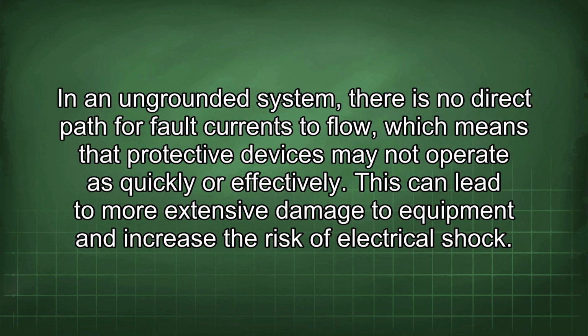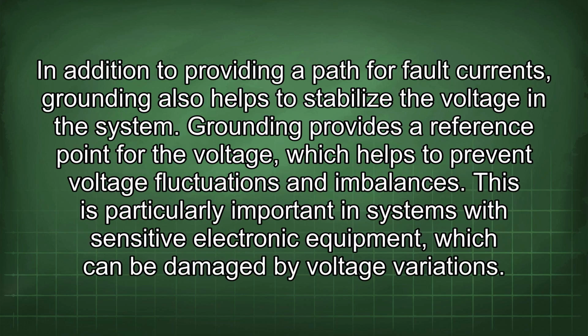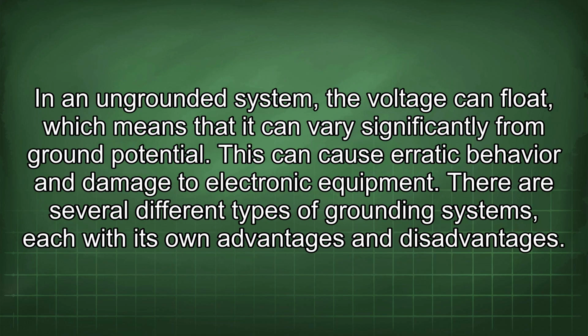In an ungrounded system, there is no direct path for fault currents to flow, which means that protective devices may not operate as quickly or effectively. This can lead to more extensive damage to equipment and increase the risk of electrical shock. In addition to providing a path for fault currents, grounding also helps to stabilize the voltage in the system. Grounding provides a reference point for the voltage, which helps to prevent voltage fluctuations and imbalances. This is particularly important in systems with sensitive electronic equipment, which can be damaged by voltage variations. In an ungrounded system, the voltage can float, which means that it can vary significantly from ground potential. This can cause erratic behavior and damage to electronic equipment.